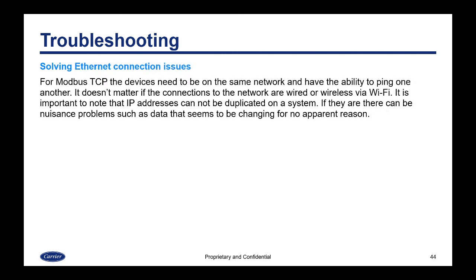For Modbus TCP, the devices need to be on the same network and have the ability to ping one another. It doesn't matter if the connections to the network are wired or wireless via Wi-Fi. It is important to note that IP addresses cannot be duplicated on the system — if they are, there can be nuisance problems such as data that seems to be changing for no apparent reason.